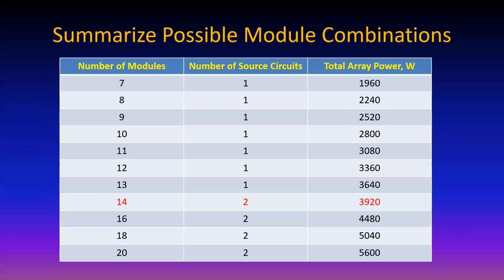All right, so we can summarize possible configurations here, but we have 14 modules, and with 14 modules, we're going to need 2 source circuits because we can't have 14 in one circuit, we can only have 13, but we can have 7, so therefore we have 2 groups of 7, and that will give us 3,920 watts from that array of 14 modules.